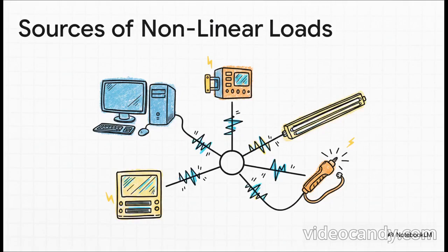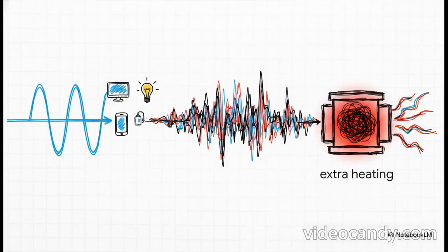All of these devices here are what we call non-linear loads. Now, unlike a simple heater that draws a nice, smooth, continuous wave of current, these modern electronics draw their power in short, abrupt pulses. Think of it like they're sipping power incredibly quickly instead of taking a long, smooth drink. And all these abrupt little sips of power, they distort the clean, smooth wave of electricity coming from the grid. They essentially add a kind of high-frequency static, or noise, onto the power line.